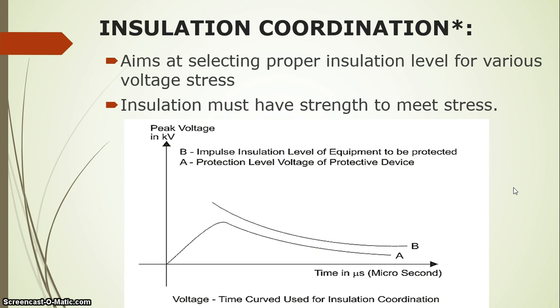The switching impulse has a wave shape of 250/2500 microseconds. Here, A is the protection level voltage of the protective device and B is the impulse insulation level of the equipment to be protected. To protect a device with protection level voltage A, the insulation level must have a much higher value to withstand against that protection level voltage.